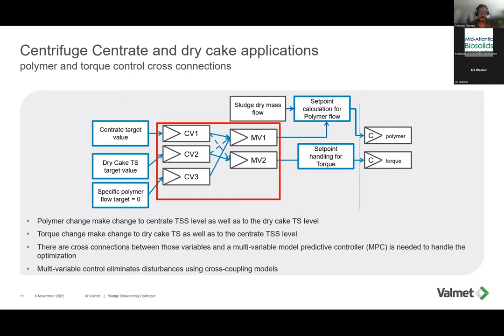For example, if you're doing a polymer change, so increasing polymer, obviously your centrate stream will change as well as the dry cake stream will change in terms of concentration. If you're making a torque change, then your dry cake will change and your centrate also changes. So what this slide tries to show is that there are cross connections between those variables, and you cannot decouple those processes or variables and manage them properly. So that's when model predictive controllers come into play, which are made specifically for these types of processes.